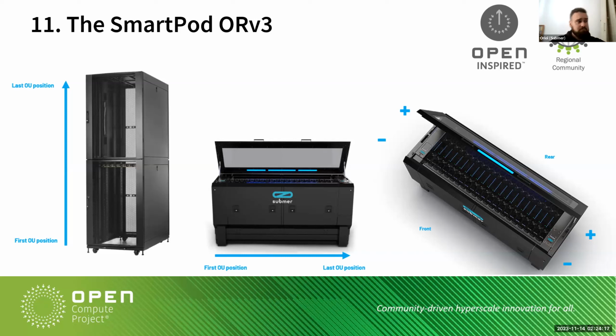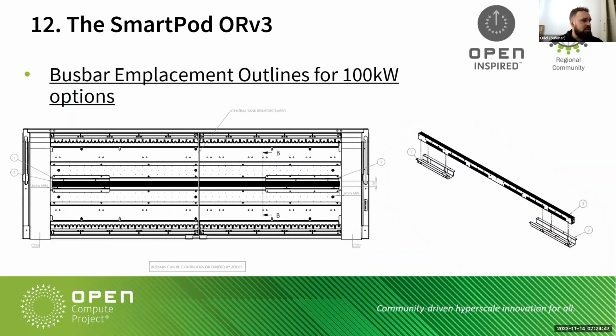Basically what we have done is take a vertical air rack and turn it horizontal. We define where the negative and the positive is, and then we place the busbars in the bottom of the tank according to that, respecting some safety elements, and install power shelves vertically that provide power to the servers. This also helps a lot for deployments, because you don't need to rely on a lot of power cables connected to a single server, since the power is distributed over the busbar, making it a cleaner environment to operate immersion tanks.